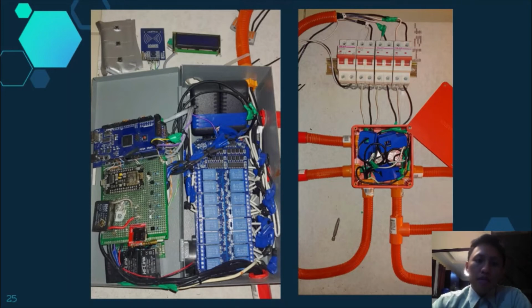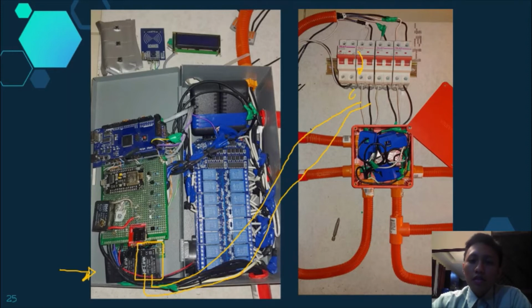What happened there is that we have connected a 230 volts AC to 5 volts DC converter, which is this one, with the inputs of the converter. So for example, we'll be using converter number 1. With the inputs of the converter tapped into the output of the corresponding circuit breaker. Since we turned off the circuit breaker, then there should be a 0 volts signal here, resulting to 0 volts signal on this terminal, and again resulting into a 0 volt signal on the output terminals of the converter.